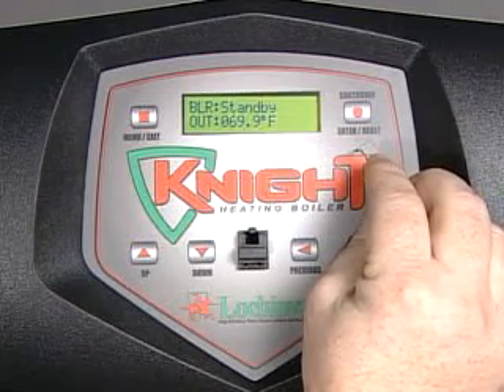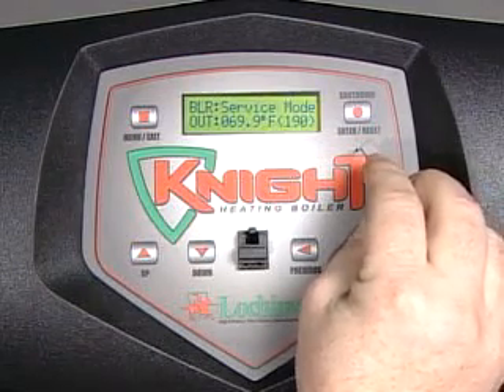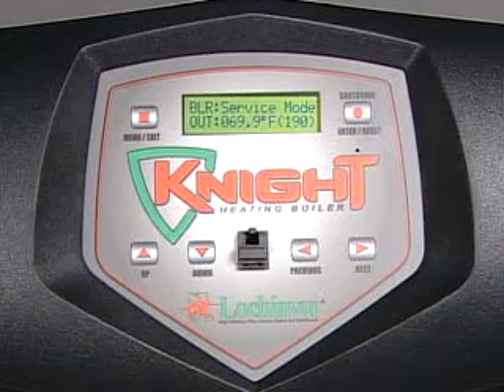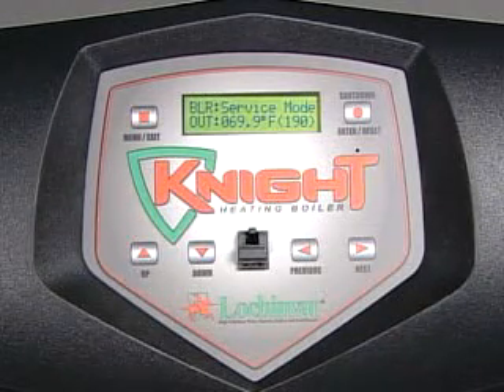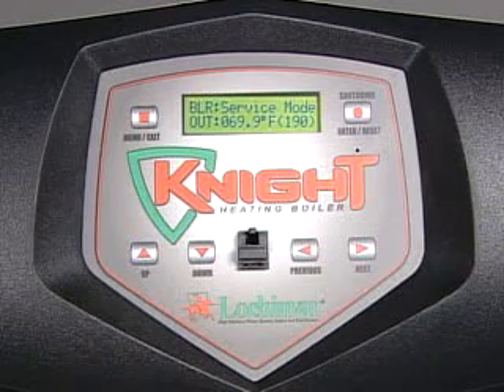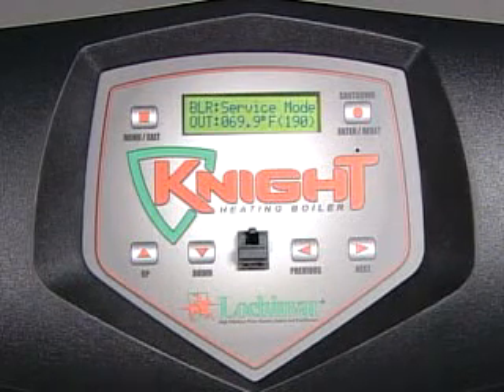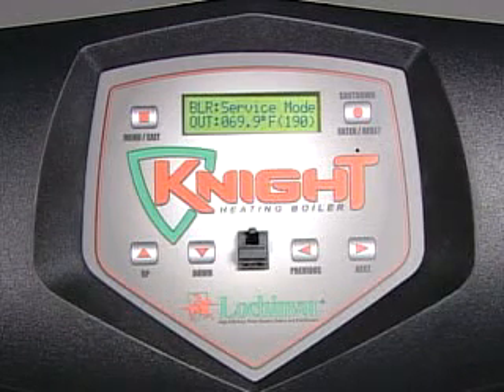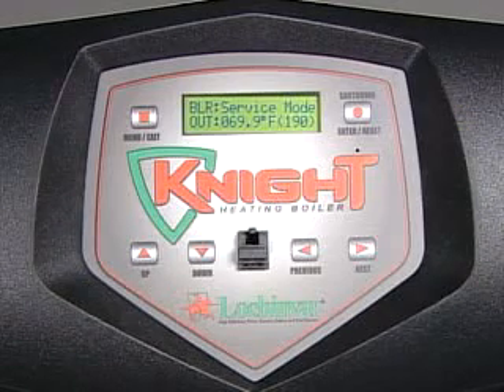The message service mode will appear on the display. The unit will fire at its normal ignition speed and will then modulate its firing rate to 100%. During service mode, the control will ignore all other heat demands. However, all safeties and maximum set point temperatures will be active.